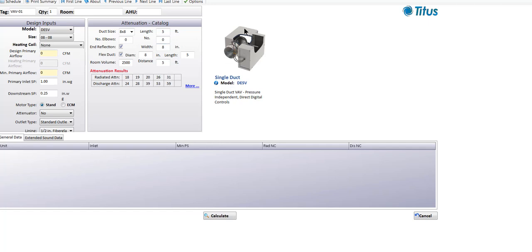If you look at the picture of the single duct VAV box, there are a few things to know about how it's configured. They normally have round inlets, which are the most efficient way to deliver air to the zone — air is round. The rectangular casing is usually sized to be at least twice the cross-sectional area of the inlet duct, so that as air passes over the damper, it expands to fill the casing, giving us static pressure regain. This lowers the static pressure requirement to move design air to the room.